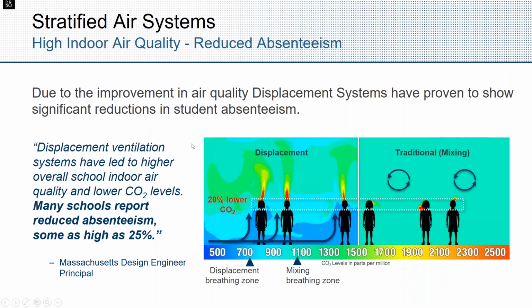This was a CFD study we did for the classroom environment—one school up in Canada comparing traditional with displacement ventilation and how CO2 levels move through the space. You can see the thermal plumes doing the job, moving the higher parts-per-million CO2 exhaled by students immediately out of the breathing zone.